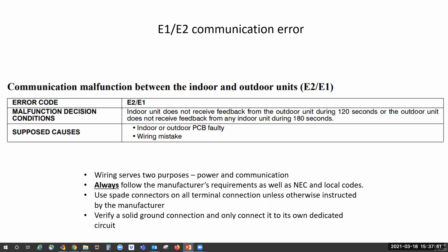Types of wire needed: 14/3 with the ground, 14/3 shielded stranded wire with the ground, with a 600 volt insulation rating. Power and communication wiring on the outdoor unit will consist of 4 wires. You'll have line voltage going through 2 of them, L1, L2, then your signal wire will be communication wire, and then you'll also have your ground wire. Now, wiring between the indoor and outdoor unit is polarity sensitive.